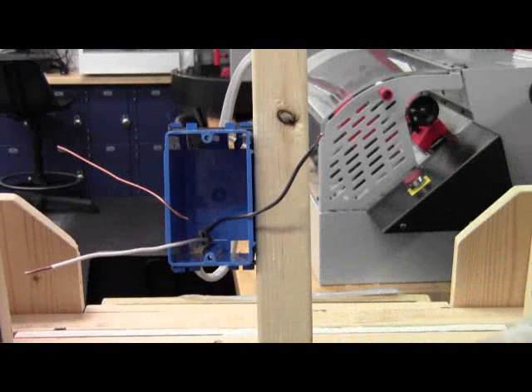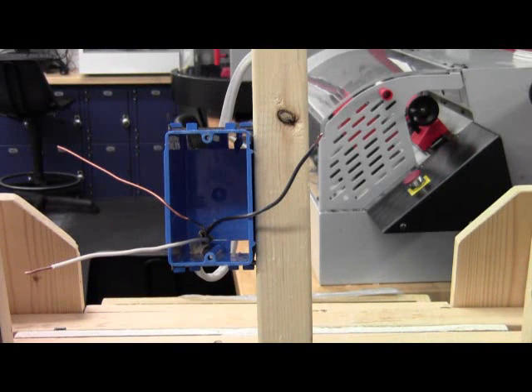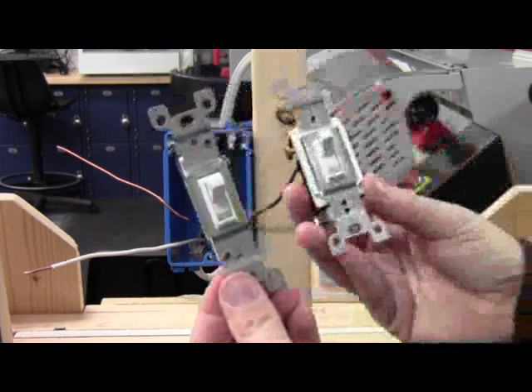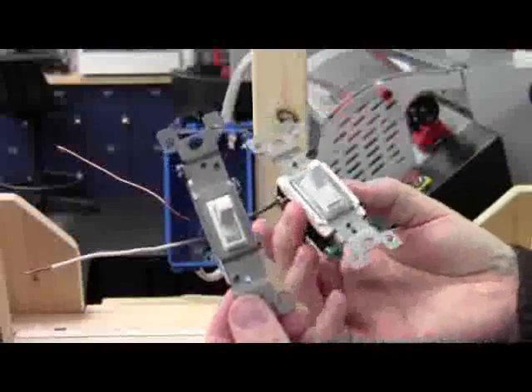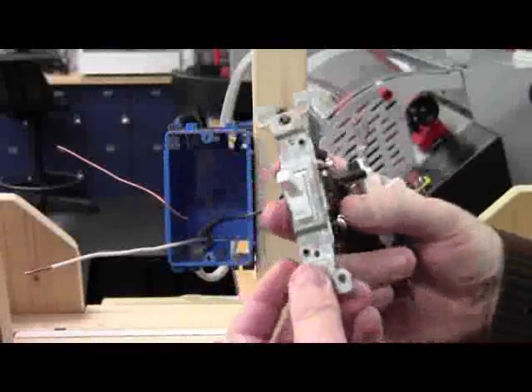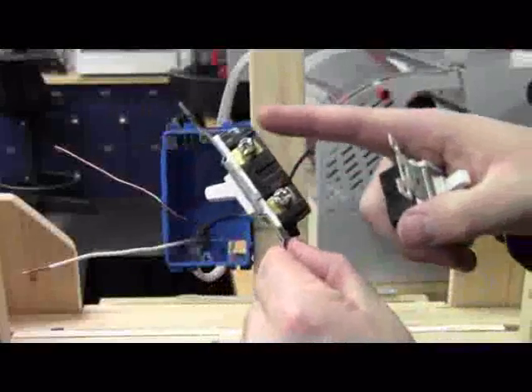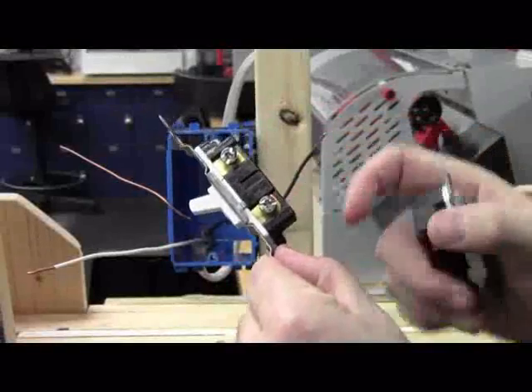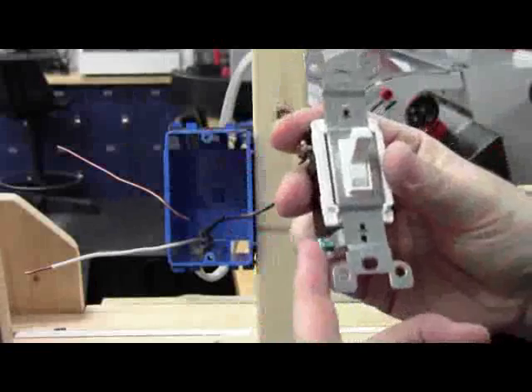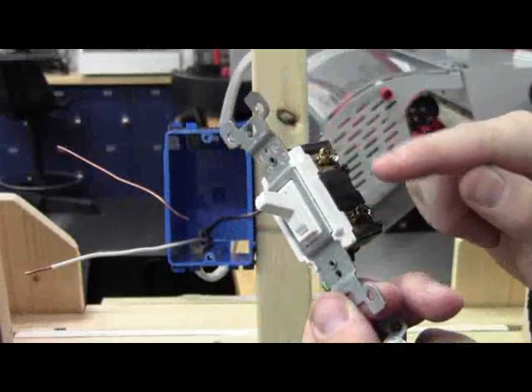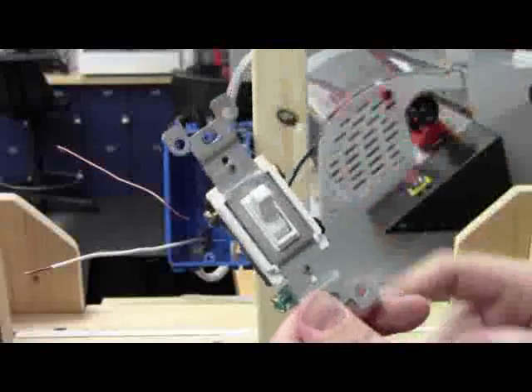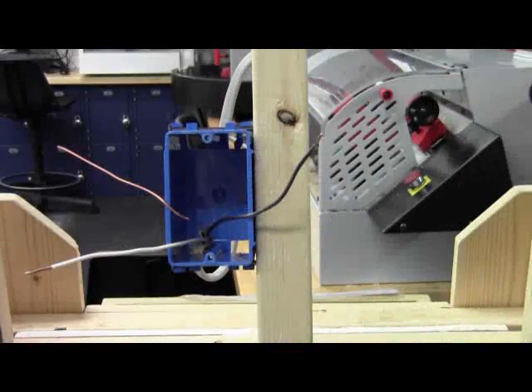Now, there's two different kinds of switches in these bags. You've got this kind and this kind. The difference is this one's a little wider. But the real difference, this is a single pole switch. You have two posts on it plus your ground screw up here. On this one you have your ground screw but you also have three posts. This is your three-way switch and we'll get into that in another lesson.